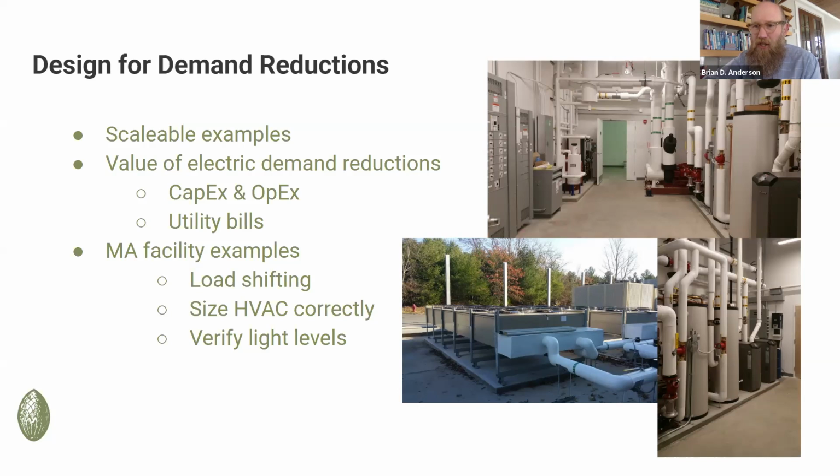So by staging those 2 opposite from each other, you essentially flatten the load so that there's never a 2-room peak, correct? Correct. So we are able to actually transfer the cooling load from room A over to room B as that shift occurs. If both of those rooms are on, you could see immediately that your cooling load is doubled, because both of your rooms are on at one time. They both have to be cooled.